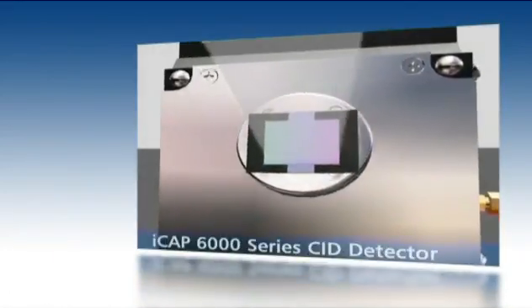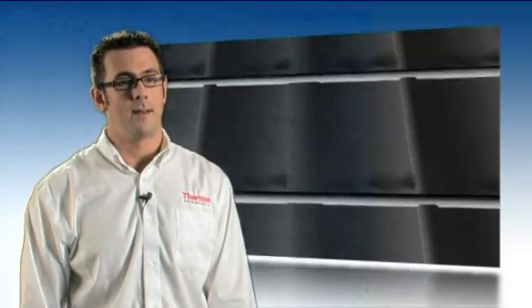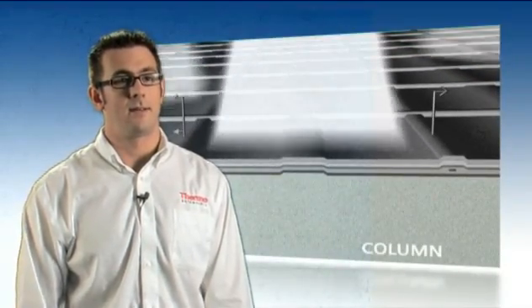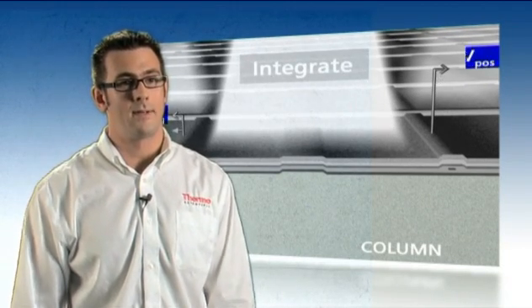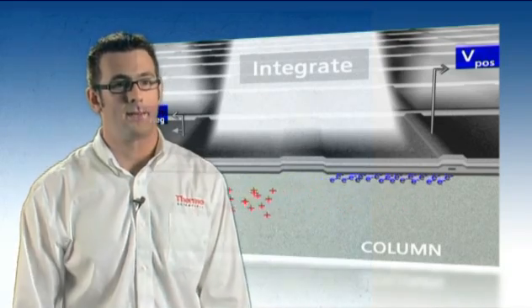We also use our own unique charge injection device, or CID, detector technology in the iCAP, and we've taken this approach deliberately because it enables a very wide and continuous wavelength coverage. The use of this detector enables our customers to access over 55,000 analytical wavelengths, giving them all the tools they need for their method development and sample analysis.